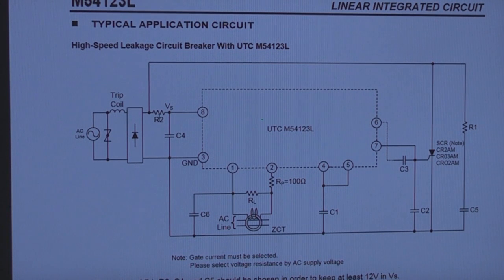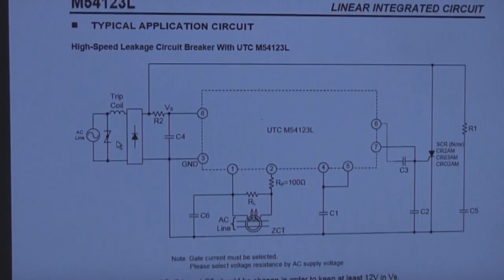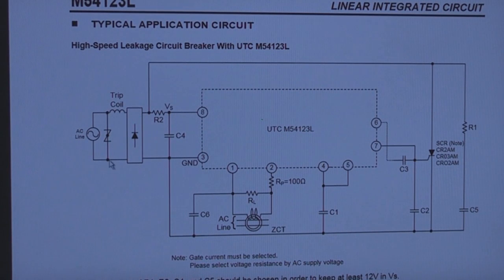There's also this resistor and capacitor here, and we've got our current transformer input here, and the output actually goes to this thyristor. So what happens is when it trips, it basically shorts out this supply, which provides a high current through this trip coil. So we've just got basically a two-wire connection to the mains, and then the current transformer thing. So the connections are nice and simple.